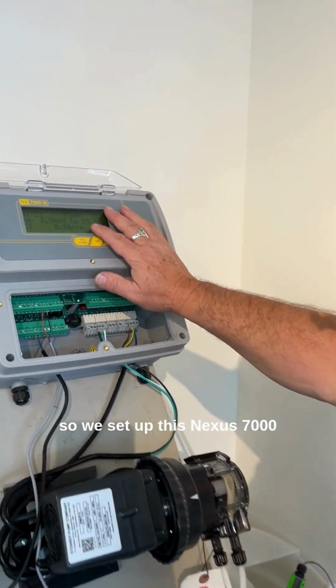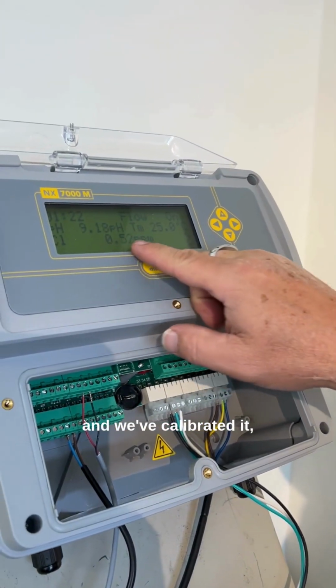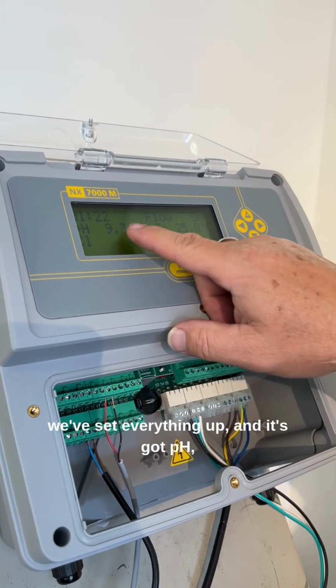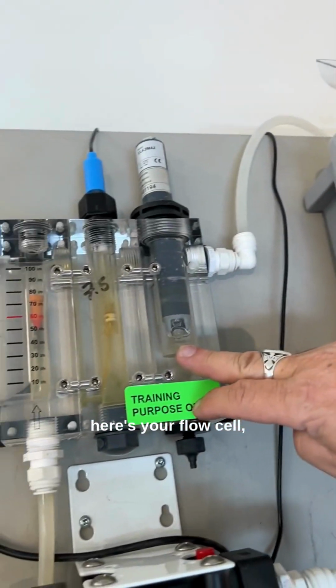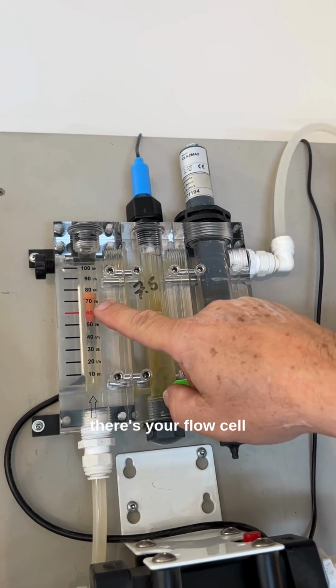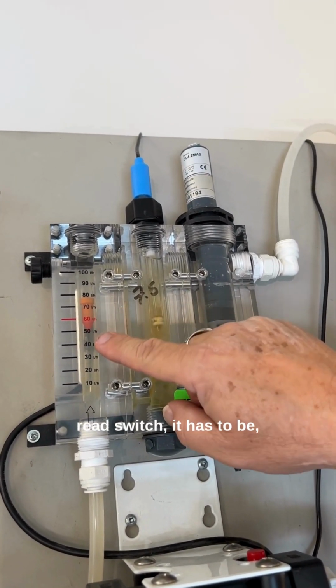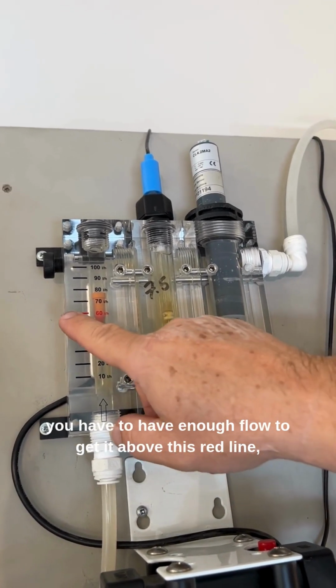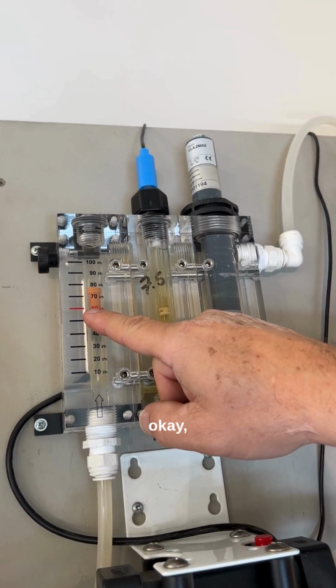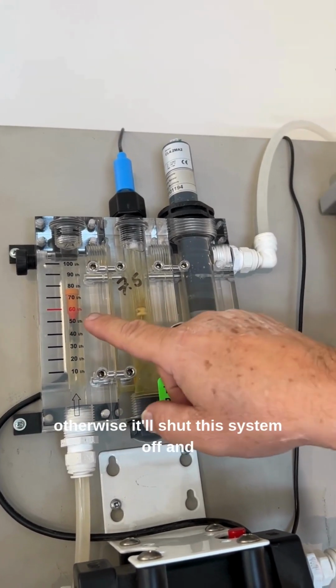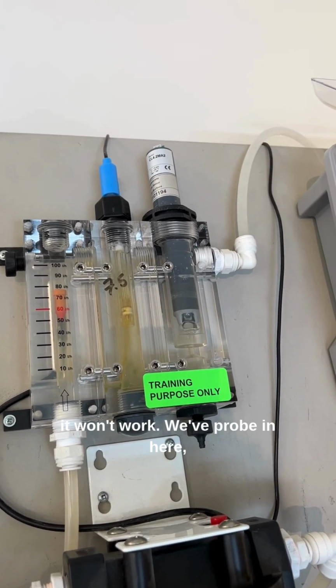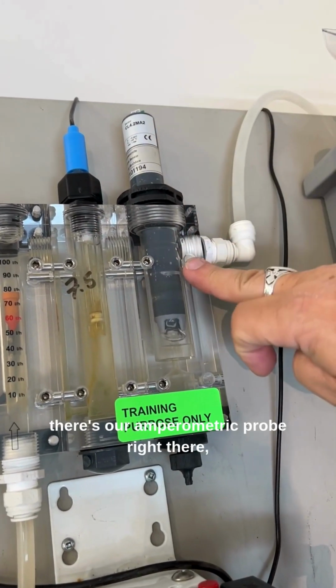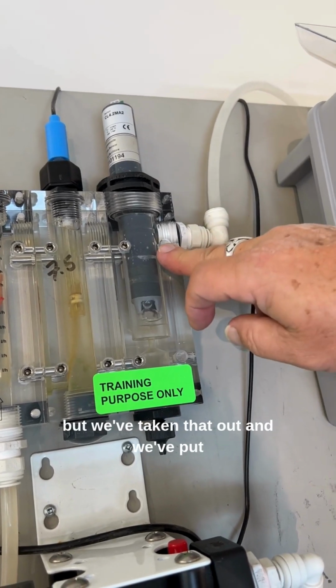Okay, so we set up this NEXUS 7000 now for chlorine, and we've calibrated it. We've set everything up, and it's got pH. Here's your flow cell. There's your flow cell reed switch. You have to have enough flow to get it above this red line, otherwise it'll shut this system off. It won't work. pH probe in here. There's our amperometric probe right there.